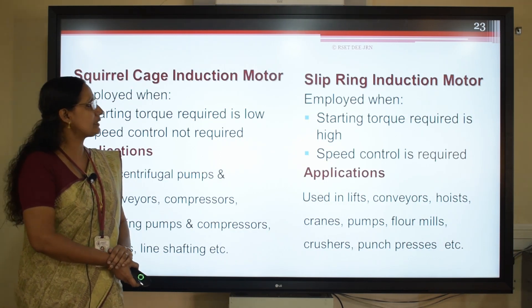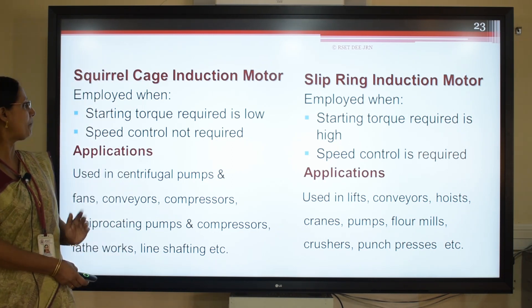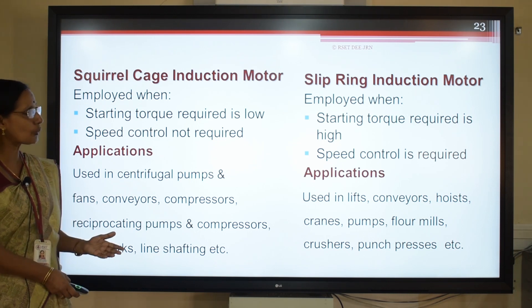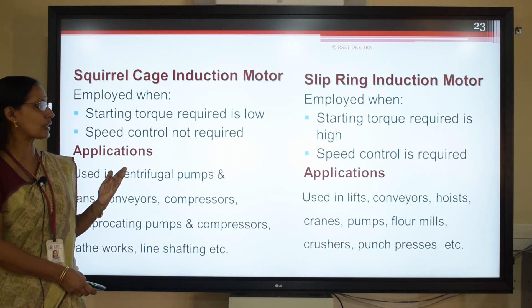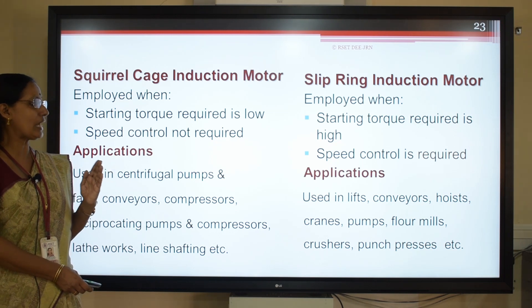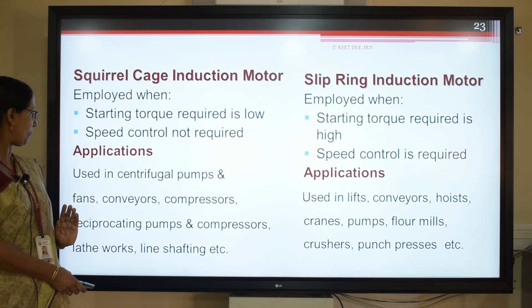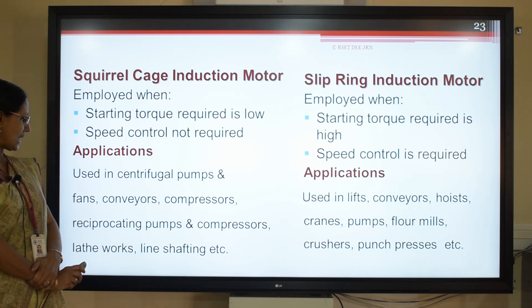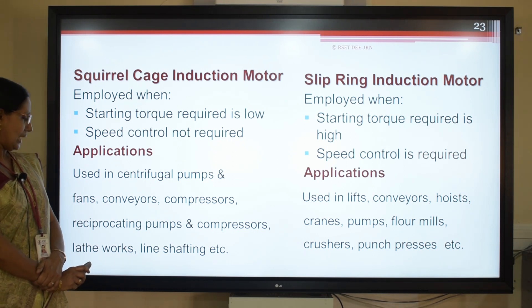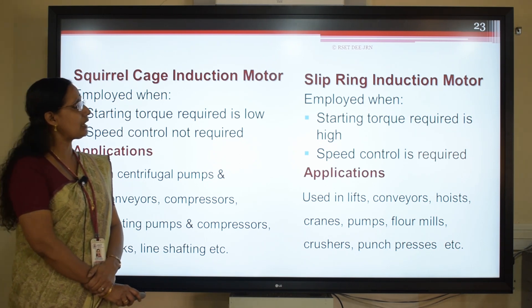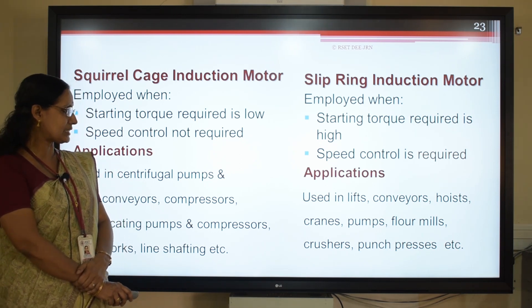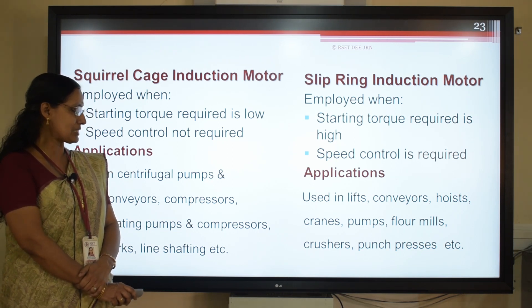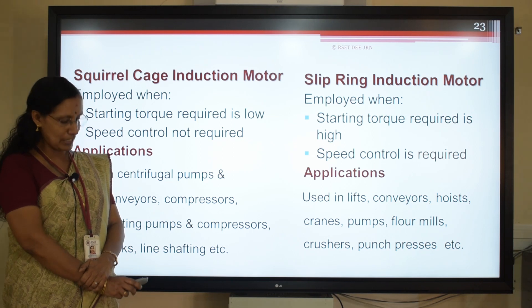Squirrel cage induction motors are employed when starting torque required is low and speed control is not required. Slip ring induction motors are employed when starting torque required is high and speed control is required. Applications of squirrel cage induction motor include centrifugal pumps, fans, conveyors, compressors, reciprocating pumps, lathe works, and line shafting. Slip ring induction motors are extensively used in lifts, conveyors, hoists, cranes, pumps, flour mills, crushers, printing presses, and punch presses.